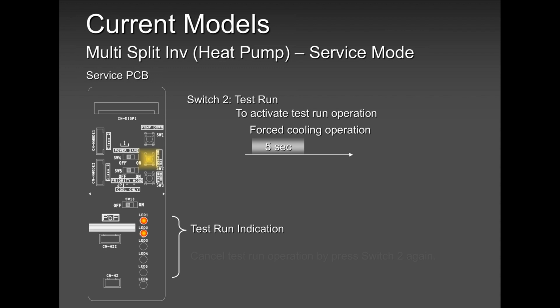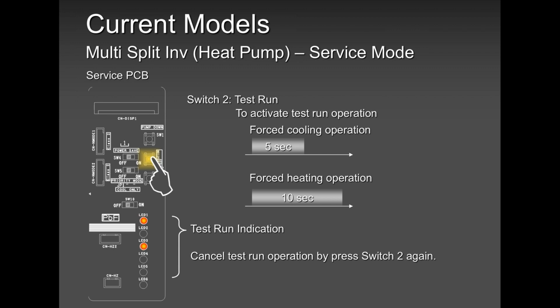You press and hold for 5 seconds. You're in test run cooling with the two lights, with the two top lights. If you keep pressing, the second light will go off, the third light will come on. You are in test run heating. Those are the two things all you need to know. Test run cooling, test run heating. So test run cooling is these two buttons, the two top buttons. Test run heating is the first and the third. Okay? And again, if you cannot remember, always read the manual. If you have no time to read the manual, give us a call, we will help you.